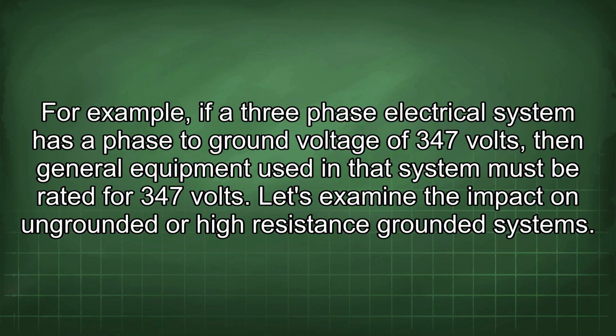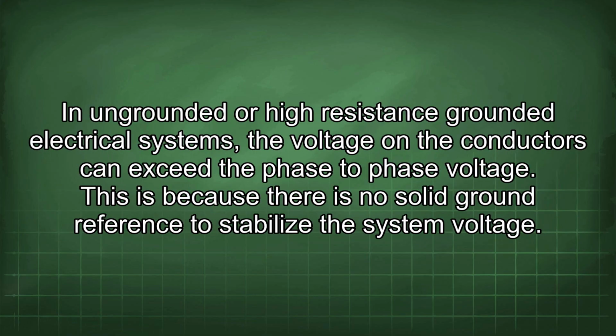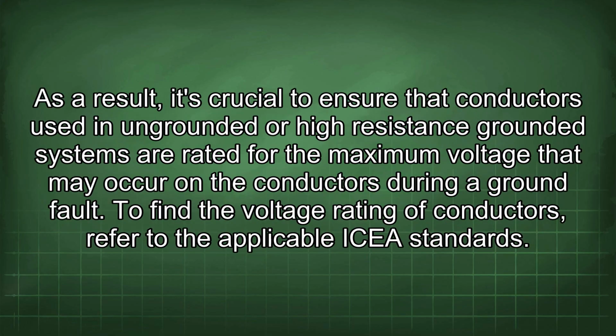Let's examine the impact on ungrounded or high-resistance grounded systems. In ungrounded or high-resistance grounded electrical systems, the voltage on the conductors can exceed the phase-to-phase voltage. This is because there is no solid ground reference to stabilize the system voltage. As a result, it's crucial to ensure that conductors used in ungrounded or high-resistance grounded systems are rated for the maximum voltage that may occur on the conductors during a ground fault.